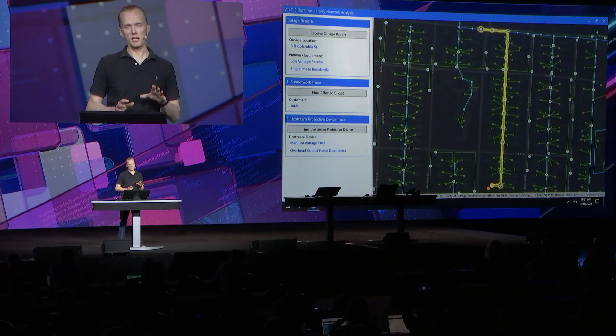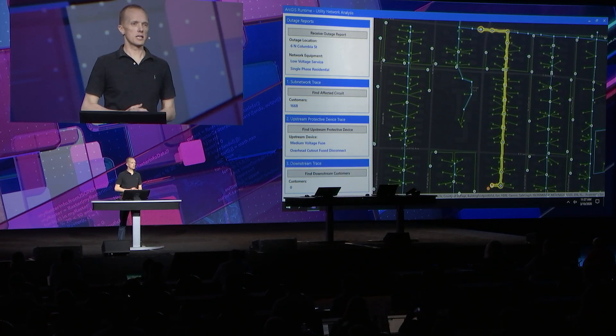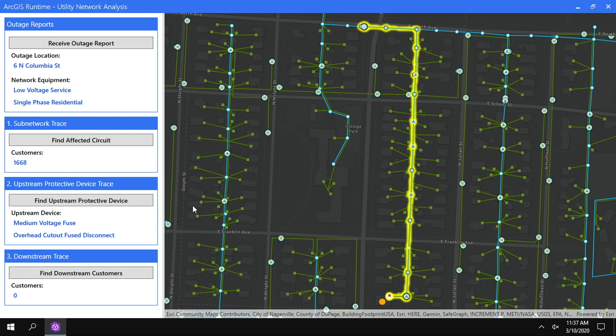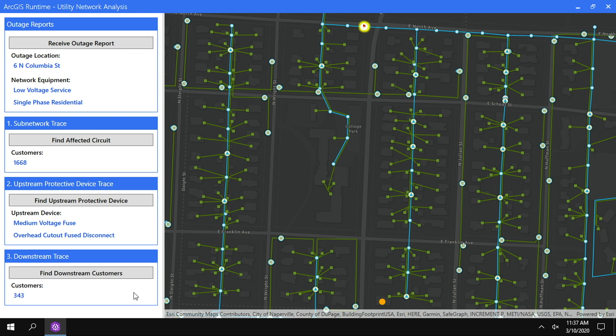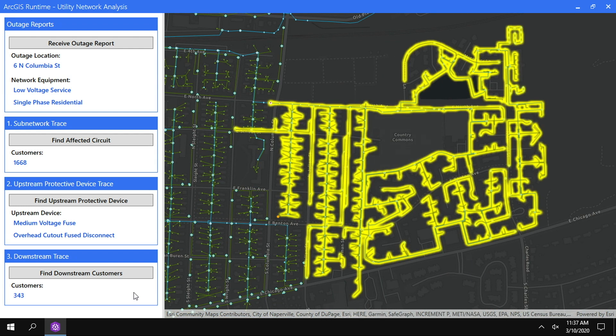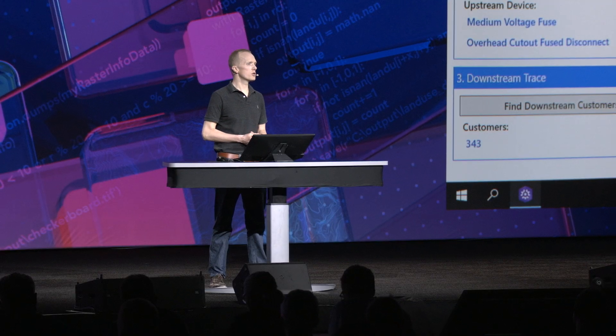The next question is: how many customers are remaining downstream from this fuse — how many people are still affected by the ongoing outage? Running another trace, this time a downstream trace filtered by the customer category, tells us that we have 343 customers still affected by the ongoing outage. We can now send them a message to alert them of the outage and of the approximate restoration time as we continue to track down the cause of the problem. ArcGIS Runtime with comprehensive utility network tracing capabilities puts the power in the hands of users, from desktop apps to mobile field apps, helping to improve reliability, safety, and customer service.